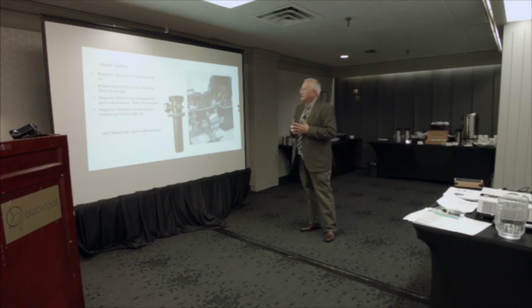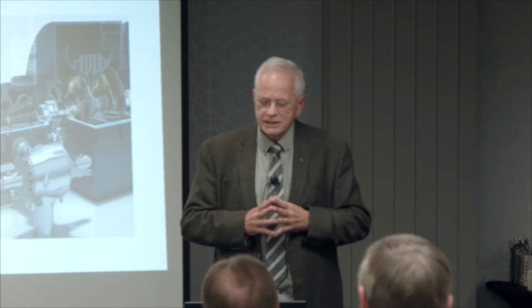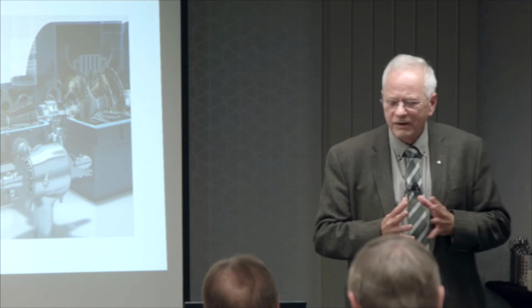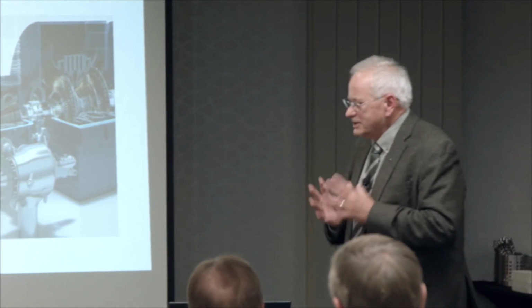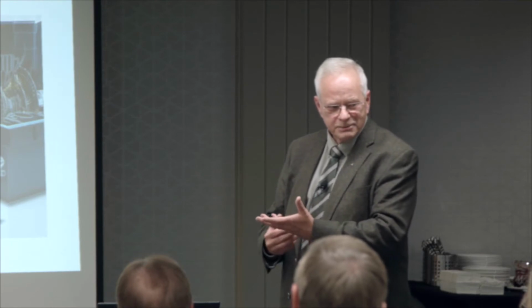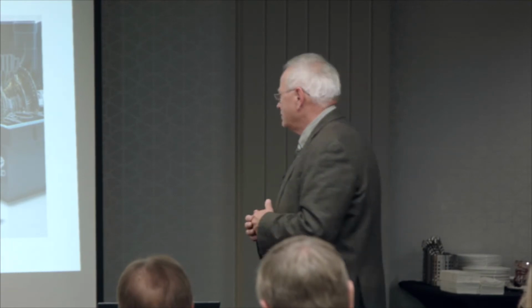We had instances where we had at least one shutdown a year that would be 4 or 5 days just to clean the contamination out of the front end pedestal. Like our overspeed bolts on a turbine were plugged. A lot of rust, and that's because of the water supply in there. Now, there's another reason for the damaged glands, and that's because when the water seal glands were replaced with steam glands, they didn't clean the system very well, and we had damage almost immediately. So we were always having water leakage problems into our oil.